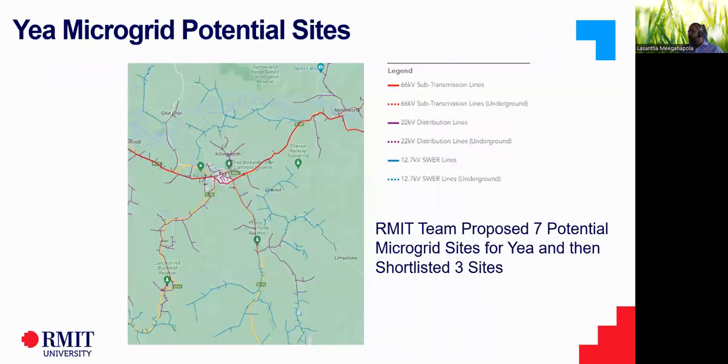So having said that, I mentioned to you earlier that we have been closely communicating with the community group. We have studied the potential of having microgrids within the community. And one thing we identified was that there is no strong case to develop a microgrid for the entire community, considering around 1,200 households. But if there are areas which are experiencing large grid outages or low reliability issues, then there could be a case.